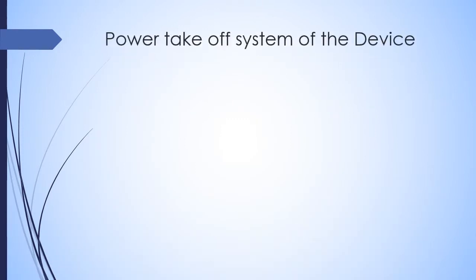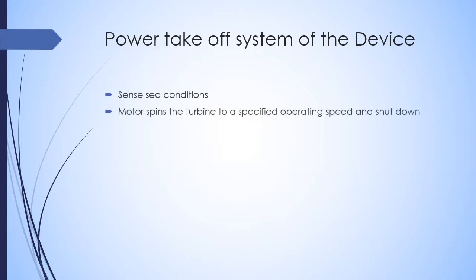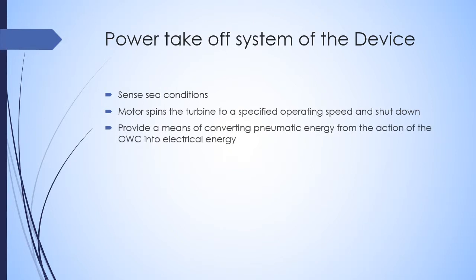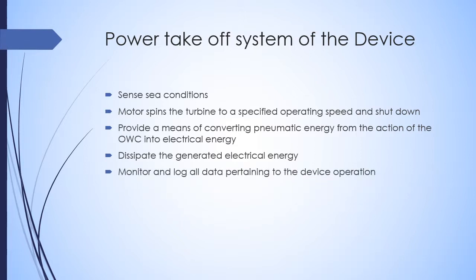The power takeoff system is the main component of this device. This senses sea conditions. A motor then spins the turbine to a minimum required torque for operation. This converts pneumatic energy into electrical energy. This dissipates the generated energy as electrical energy in the system circuit. An integrated controller monitors and logs all data pertaining to the device operation. This integrated controller is then remotely used to control the device via telecommunication links as the device is in a remote location.